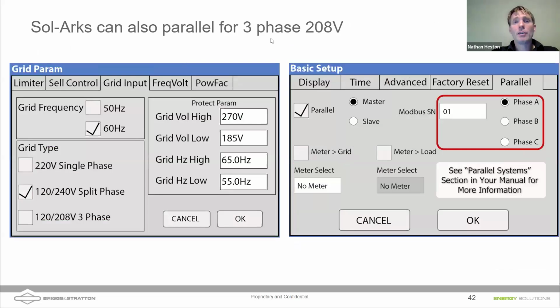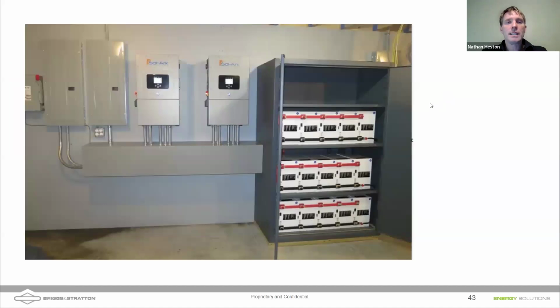Sol-Arks can also be paralleled to three-phase 208. The most common application I would think would be the split phase 120/240. So you get two legs of 120. But if you have two or more inverters, you can create three-phase 208 power out of them. And you would do that by, under your basic setup, selecting parallel inverters, and then you have the ability here to do three-phase power. But this is not the talk for that. I just want you to know that that's available if you're trying to do three-phase. Here's a nice system where we've got a couple of 12Ks, it looks like, paralleled, and I'm showing you just because it's a very nice install.